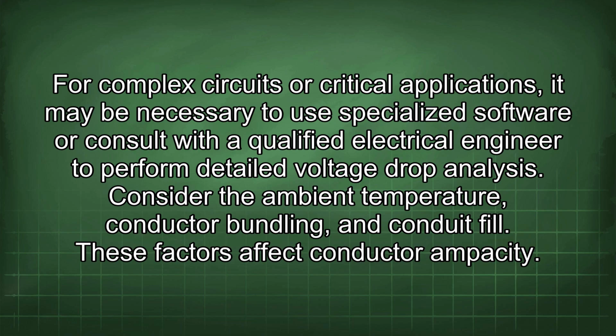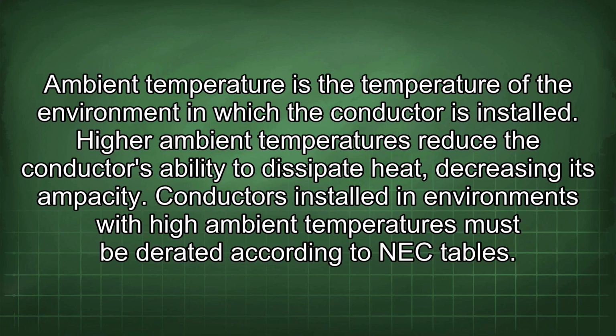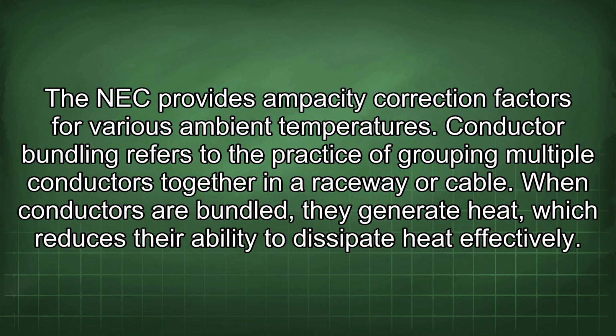Consider the ambient temperature, conductor bundling, and conduit fill. These factors affect conductor ampacity. Ambient temperature is the temperature of the environment in which the conductor is installed. Higher ambient temperatures reduce the conductor's ability to dissipate heat, decreasing its ampacity. Conductors installed in environments with high ambient temperatures must be derated according to NEC tables. The NEC provides ampacity correction factors for various ambient temperatures.